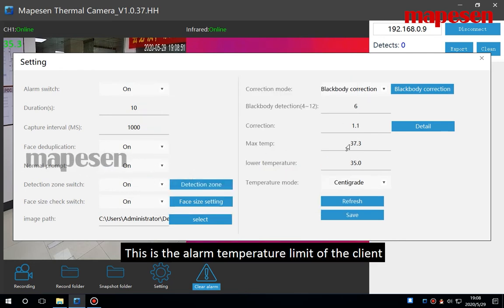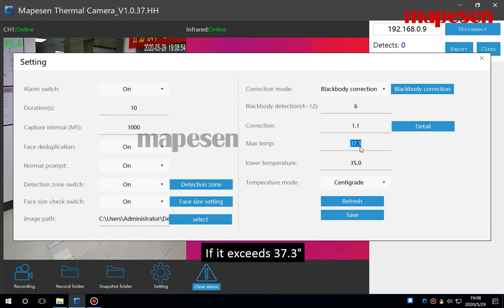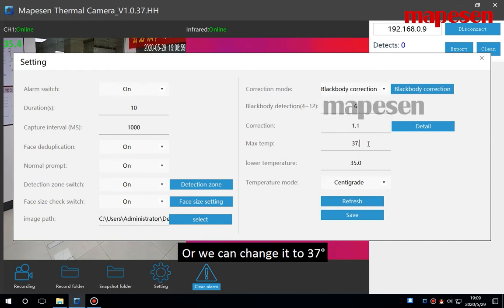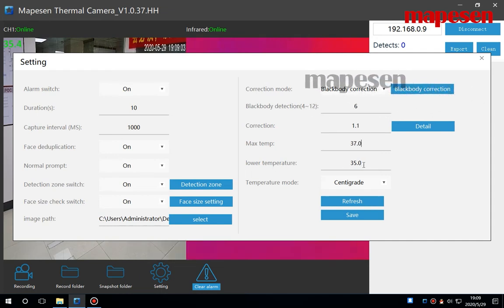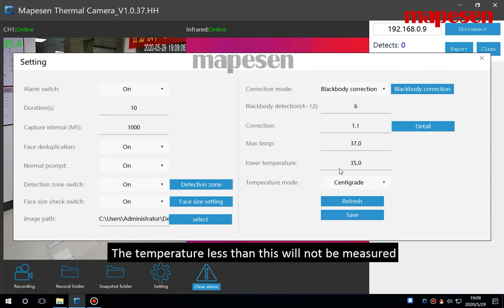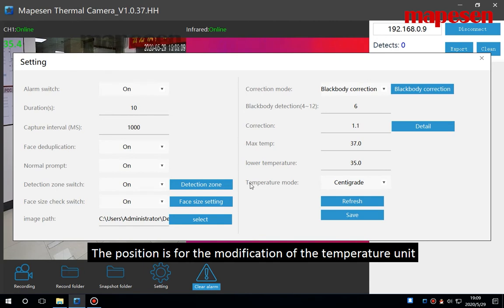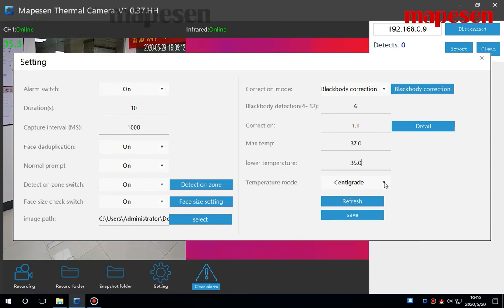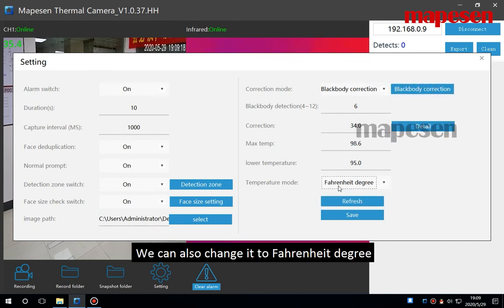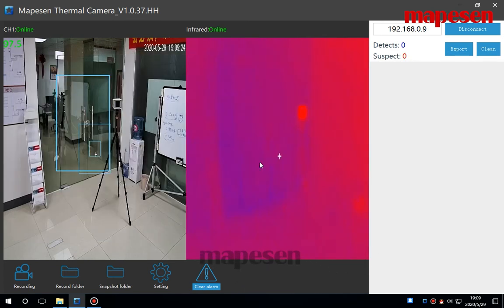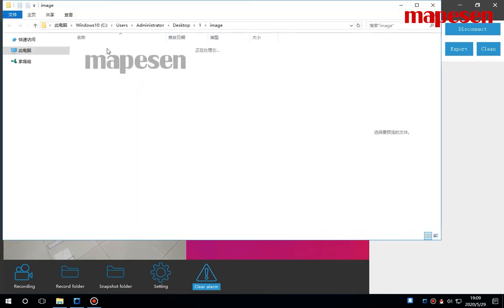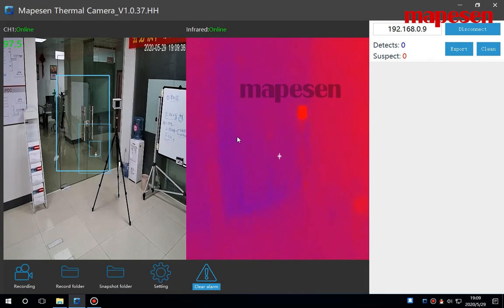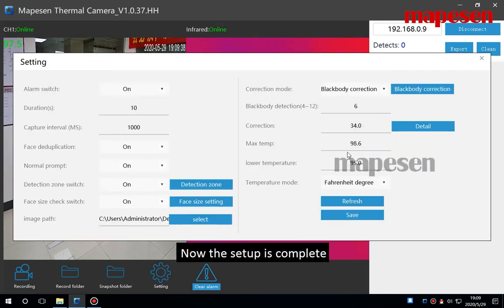This is the alarm temperature limit of the client. If it exceeds 37.3 centigrade, it will alarm. Or we can change it to 37. This is the lowest temperature setting. The temperature less than this will not be measured. This position is for the modification of the temperature unit. The default is centigrade. We can also change it to Fahrenheit. And then click save. We can see this one is the folder we just set up. The setup is complete.